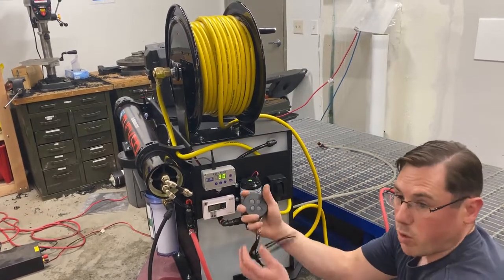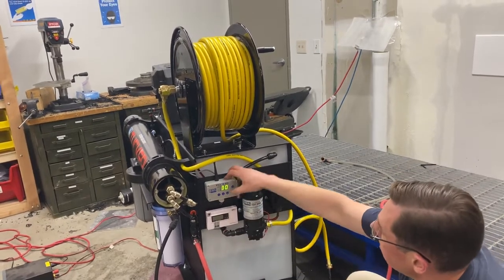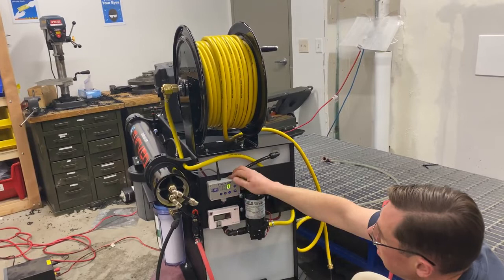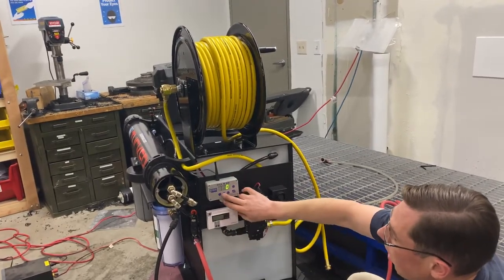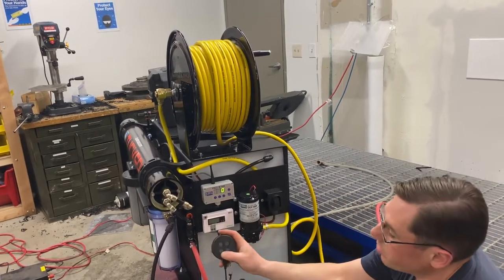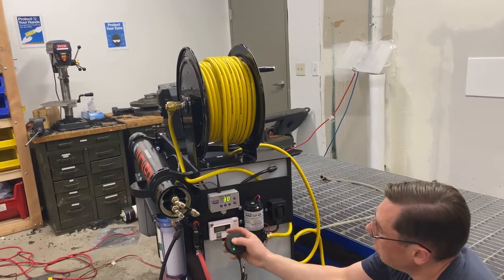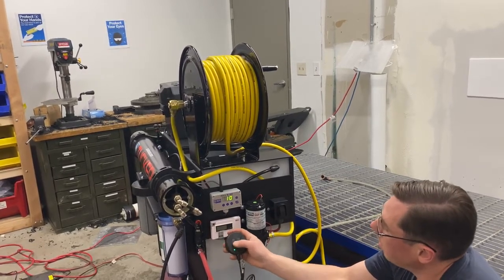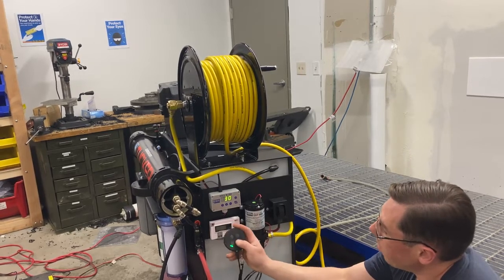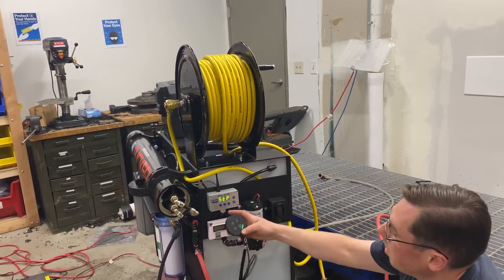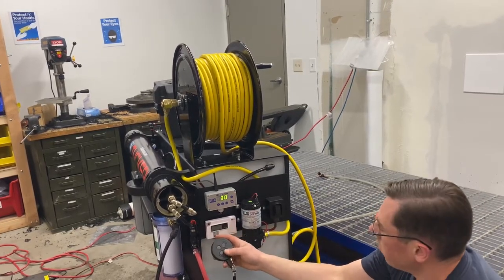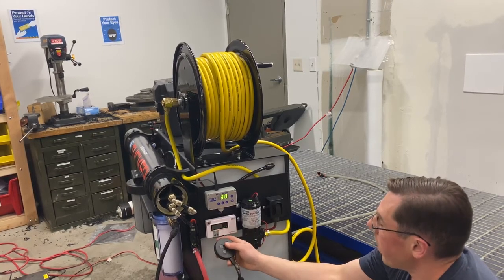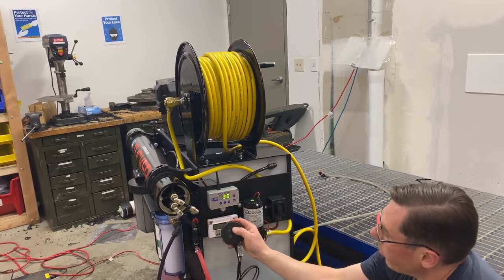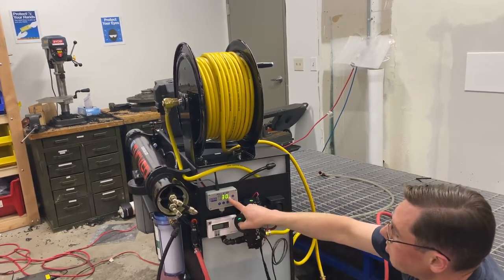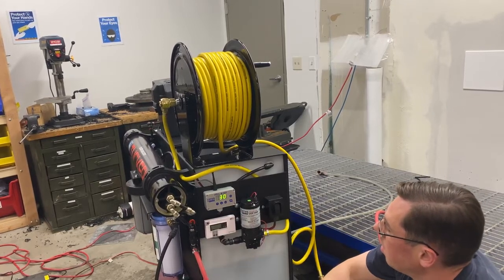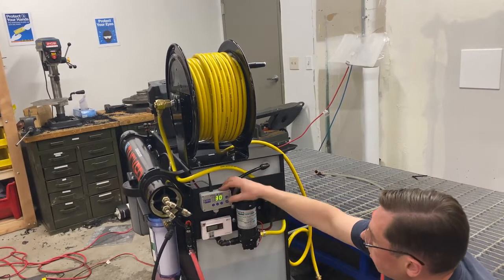Now, this unit will also come with a remote fob. This does several things. Besides being able to control up and down at the controller, you can also control with the fob. 2 is up, 1 is down. You can also hit number 4 and it'll read stop. Hit number 4 again, flow resumes. The second way to calibrate is with the fob. Hold down the number 3. It's one-touch automatic calibration. And water continues to flow.